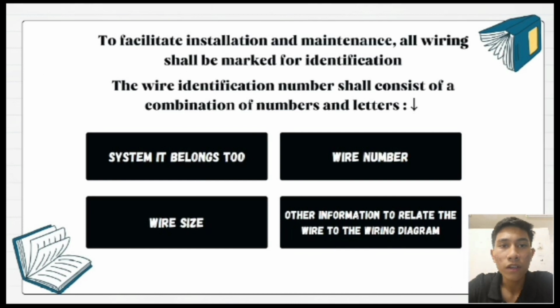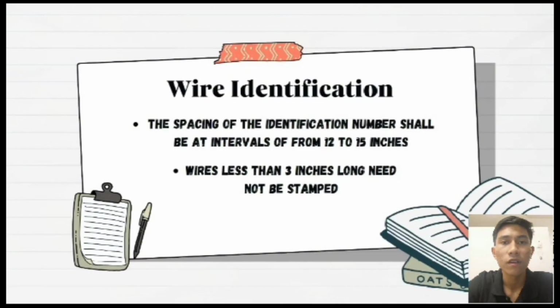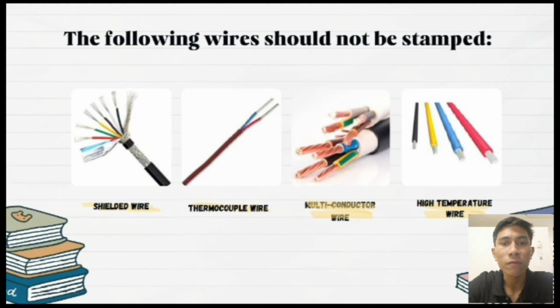The wire identification number should contain a combination of numbers and letters. It has 4 parts: the system it belongs to, wire size, wire number, and other information to relate the wire to the wiring diagram. Spacing of the identification number should be at intervals of 12 to 15 inches. Wires less than 3 inches long need not be stamped. The following wires should not be stamped.